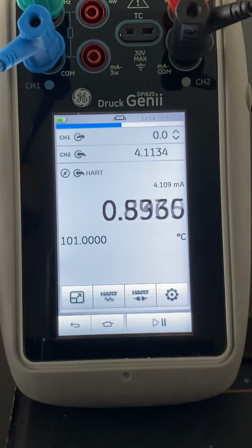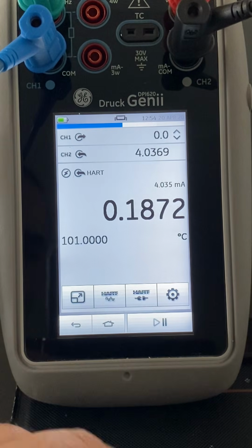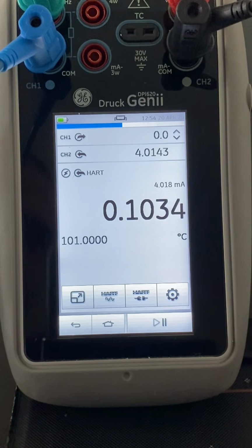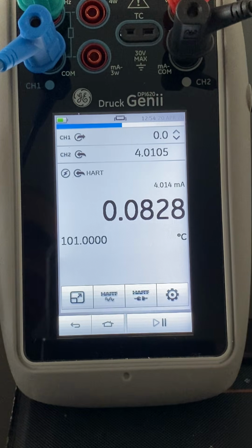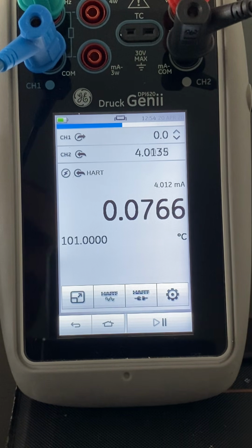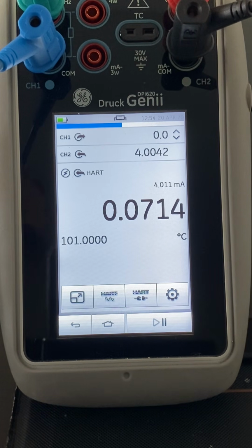So this is the HART channel. We have two applications actually. We have the HART online and we have the HART offline. The HART offline, we can use it if we wanted to work offline. So we will import the data from the transmitter, make the settings offline, and paste it back or send it back to the transmitter. We can do this to clone devices, or we can just use it as an offline mode. This is so helpful in the initial commissioning, but if the device is already in operation, we need actually to connect to the HART online.